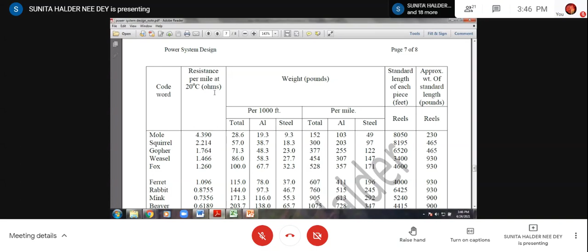So in this equation, voltage drop is not equal to del V. Actually this should be maximum, so less than or equal to this. So R will be how much, less than or equal to that? Say 0.5 you have got. Then from here you have seen that R should be less than 0.5. Then obviously less than 0.5, this conductor category will be your selected conductor.